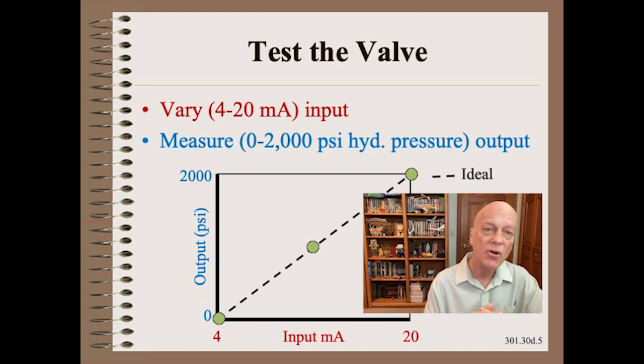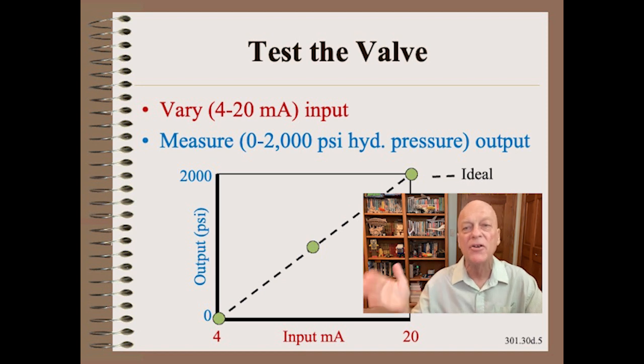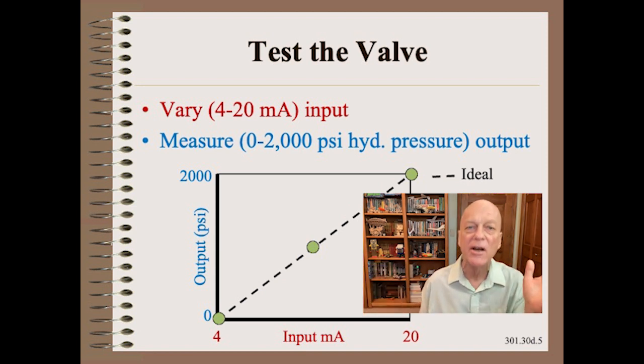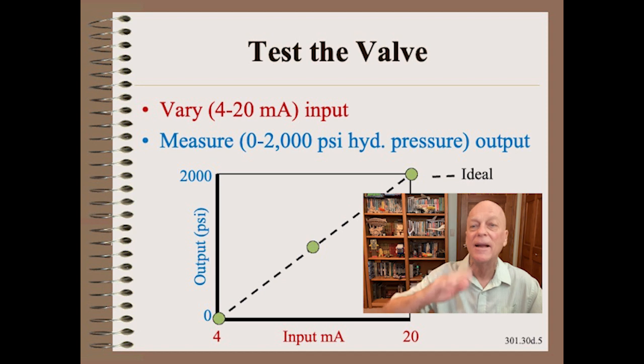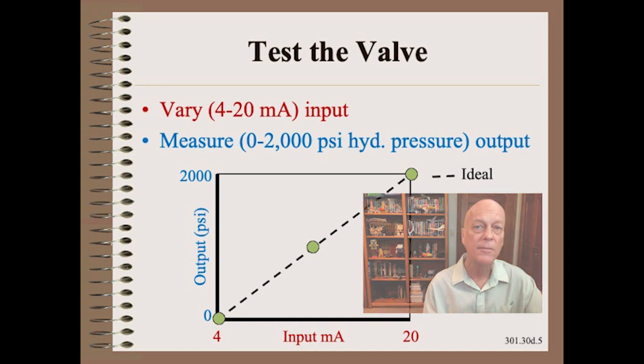The easiest thing to do was to check the performance of the servo valve by manually moving the input and then using an installed pressure gauge to read the output. Ideally, the curve should be linear and have a sensible zero. In this case, the control input was a robust 4 to 20 milliamp current signal, so that at 4 milliamps you would get zero pressure out.